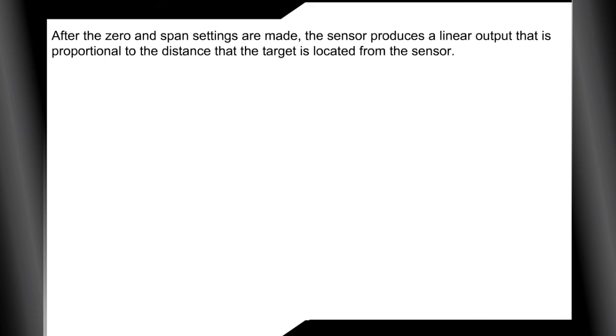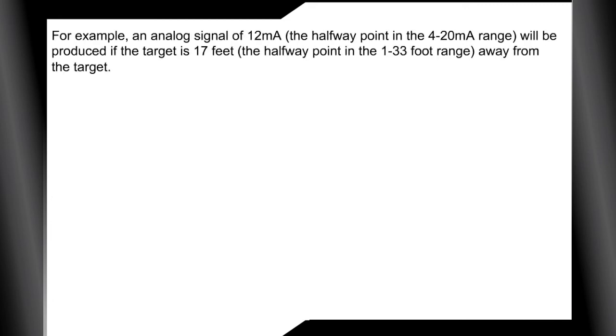After the zero and span settings are made, the sensor produces a linear output that is proportional to the distance that the target is located from the sensor. For example, an analog signal of 12 milliamps will be produced if the target is 17 feet away from the sensor.